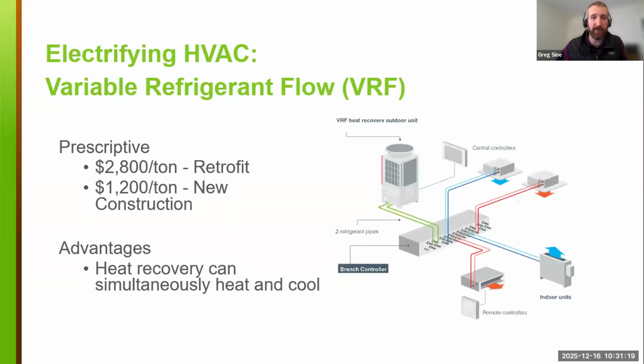We can go to the VRF. VRF is similar in some ways to the air source heat pumps we looked at before. However, they have higher efficiencies and have the ability to do what's called heat recovery, or simultaneous heating and cooling. This is pretty common in large office buildings that have a center core section, which might have a year-round cooling load. You're able to move heat from the perimeter rooms to the center. You're able to move heat around within the building to where it's needed, rather than using the outside ambient temperatures as a heat source. So that can really increase the coefficient of performance when there are year-round simultaneous heating and cooling loads.